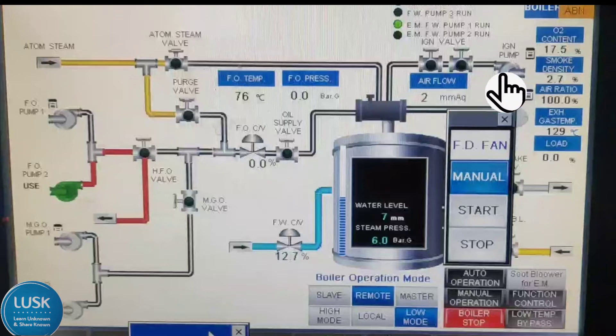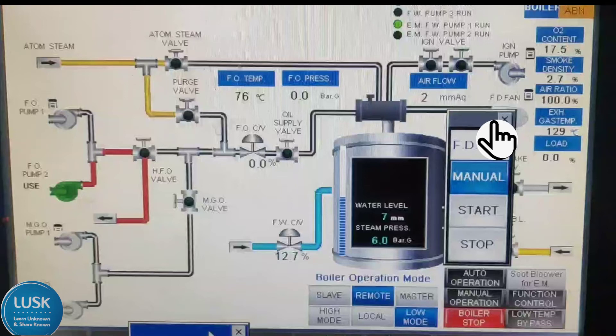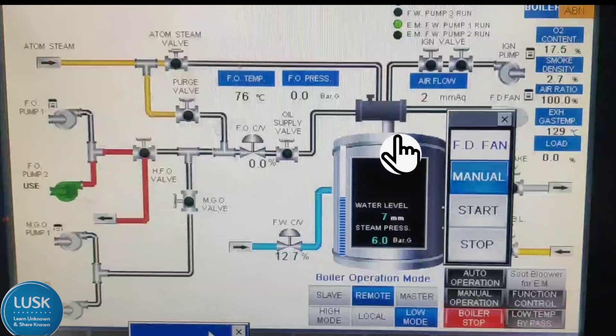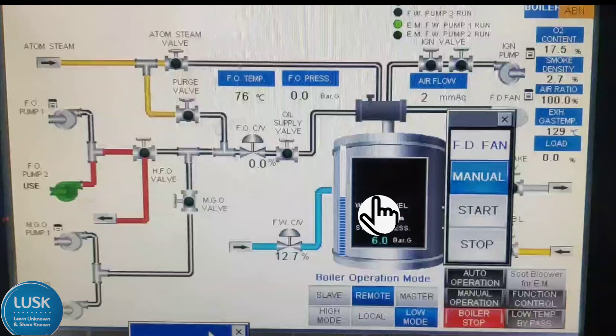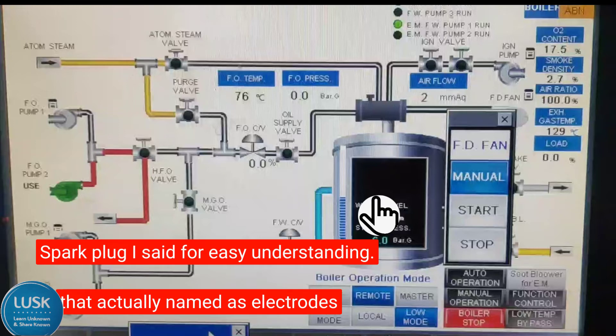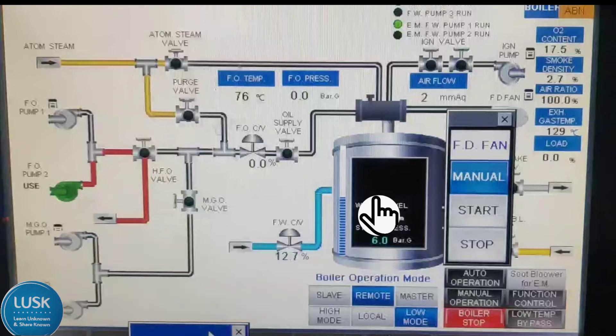Next there is an ignition pump. In big boilers there will be 2 burners inside: one is the pilot burner and the other is the main burner. For firing the pilot burner, there will be an electrode that creates a spark, and with the help of diesel oil the pilot burner will fire. The ignition pump pumps diesel oil for the burner so it will ignite and get fired. When the pilot burner fires, after that the main burner will get fuel oil and start firing. With a spark plug alone we cannot fire the main burner because the main burner is a bigger one, so we use the pilot burner to fire the main burner. After the main burner starts catching the fire, the pilot burner will stop automatically.